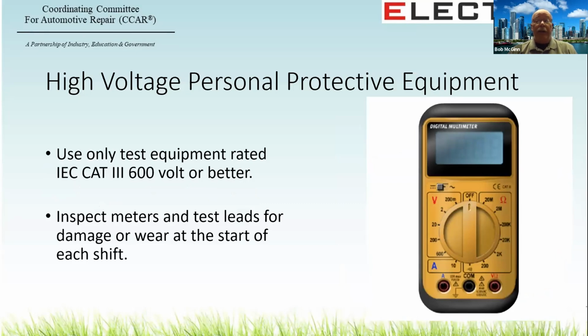Now, as far as test equipment goes, the minimum standard is IEC Cat 3 or better at 600 volts as a minimum rating. And please check your test leads, because we are talking again about students who may have damaged the test lead. And we all know, I know I did it when I was in shop class, that if I broke something, I wasn't necessarily going to be the first one to run right up and say, teacher, teacher, look what I did. But again, the difference is that at 12 volts, a short to ground would be an oops, or it's a giggle. At 600 volts, it's calling an ambulance, or it's a small fire.